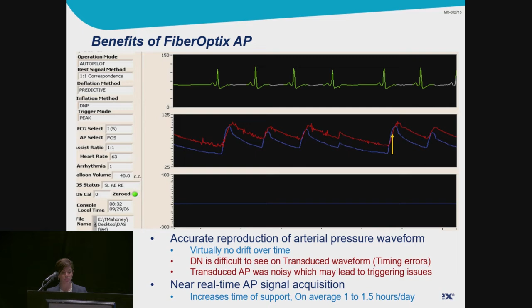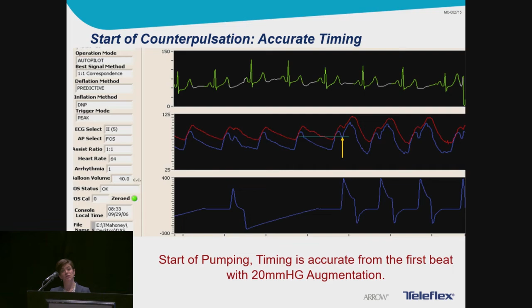Now here when we started the pump, you can see you have very quick startup and with optimal support in autopilot mode. The automatic trigger selection, timing method, and settings were done for us because again, we were in autopilot, and the pumping starts at full volume and a 1-to-1 assist. Now, timing of inflation and deflation is accurate from the very first beat, and we are seeing about 20 millimeters of mercury augmentation rise and good LV unloading.